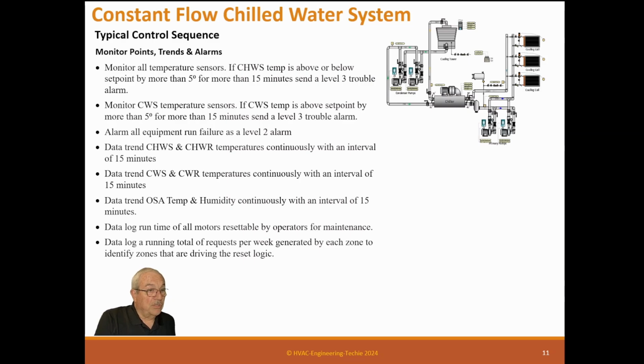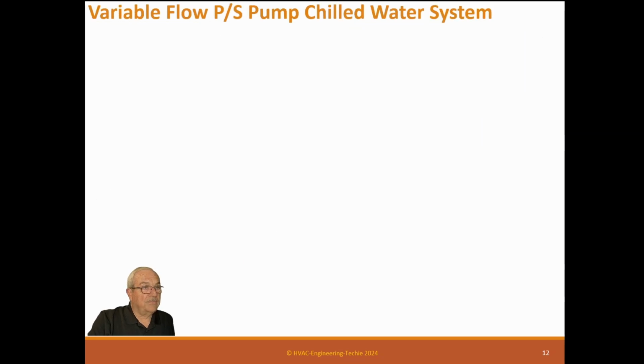You want excluded, so maybe it's an electrical room, and you certainly don't want an electrical room driving your reset, so you would remove that from your seek and response sequence. You don't even want to look at it at all.